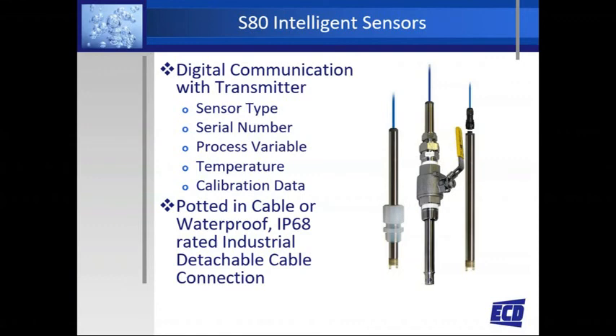So when you wire up the sensor to the transmitter, it uploads all that data to the transmitter, making the transmitter whatever the sensor is. So if you hook a pH sensor up to it, it becomes a pH instrument. If you hook up a conductivity sensor, it becomes a conductivity transmitter. No changes to the transmitter.